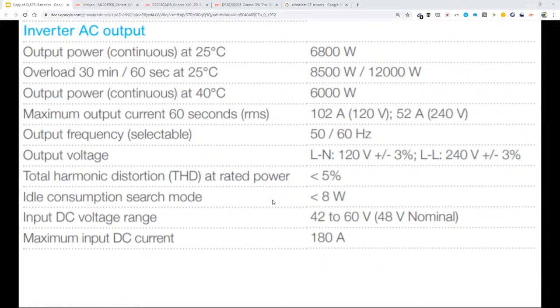So here's some ratings for the inverter output, and it's saying, okay, its total power output range is 6,800 watts. So this is a 6.8 kilowatt battery inverter, and it can actually surge. So if it goes above 6.8 kilowatts, it can do 8.5 for 30 minutes. You can also do 12 kilowatts for 60 seconds.